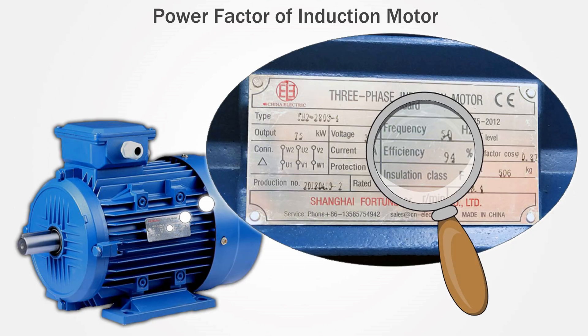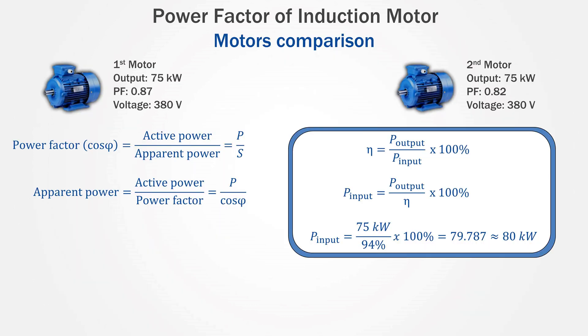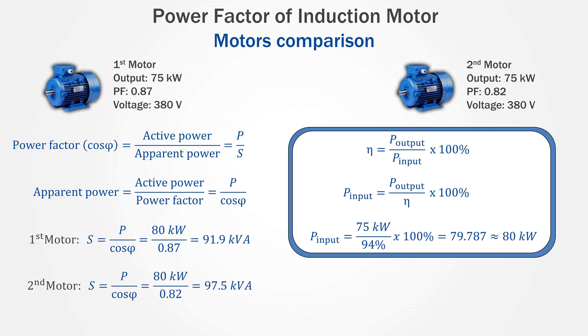Let's take a look at the nameplate of the induction motor one more time and check the efficiency of the motor. The efficiency of the motor is 94%. Substituting the values into the formula, we get the input power. The first motor will need to draw 91.9 kVA from the power supply system to provide 75 kW of power. And the second motor will need to draw 97.5 kVA from the power supply system to provide the same 75 kW of power.